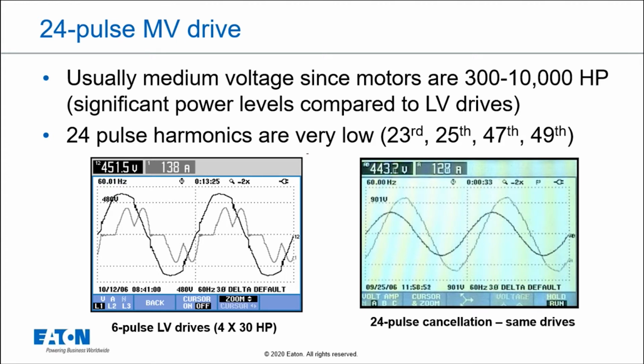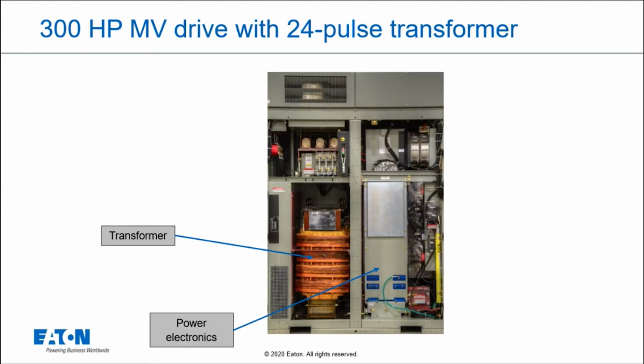So what's a medium voltage 24 pulse drive look like? This is basically the drive, the guts of it. We have the 24 pulse transformer, and we have the power electronic converter that basically is going to do the rectification and inversion. And by having 24 diodes in this case to switch from AC to DC in the rectifier part, we're enabling ourselves to minimize the harmonics coming out of the drive. Remember, again, harmonics come out of the load, in this case the drive. Let's take a look at an example now.